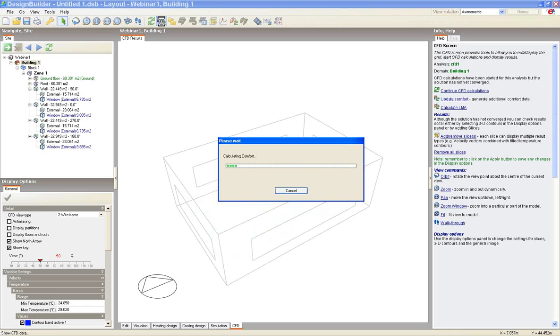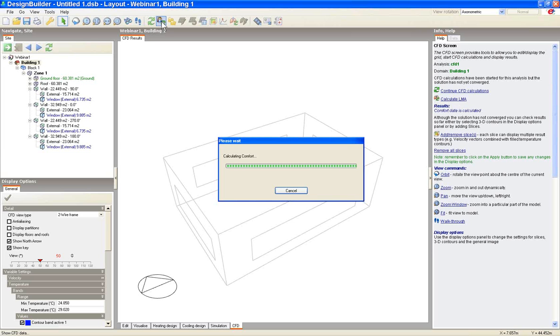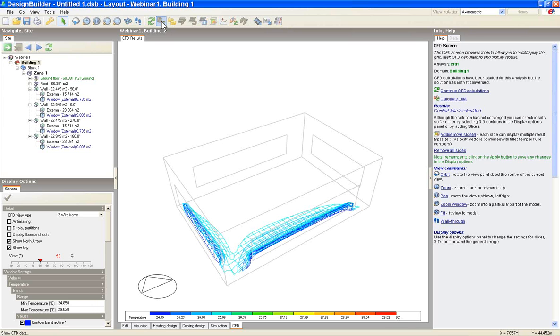Earlier I showed you where on the activity data we had the information to do with the Fanger analysis, so clothing levels, etc. Now what this does is it looks at that data, and it allows me to start plotting that data onto our CFD. So it obviously depends highly on the usage of the building and the setting that we make. So it's important that you set that up when you set up your model.